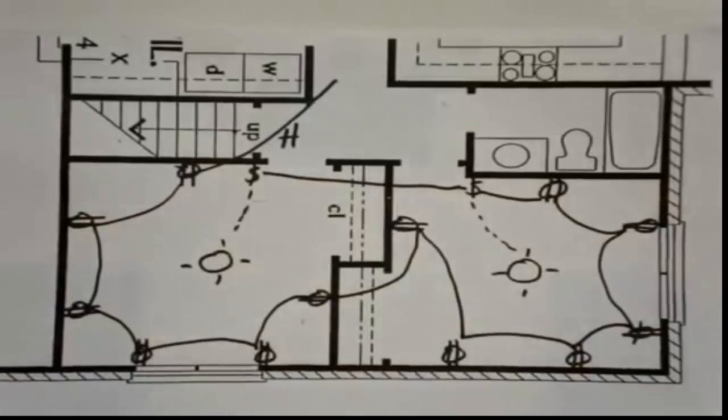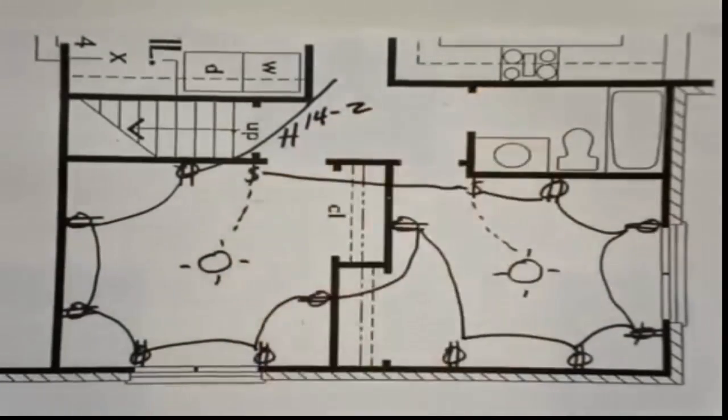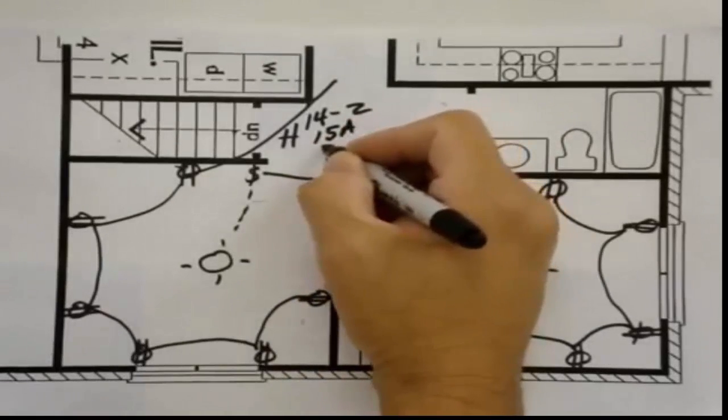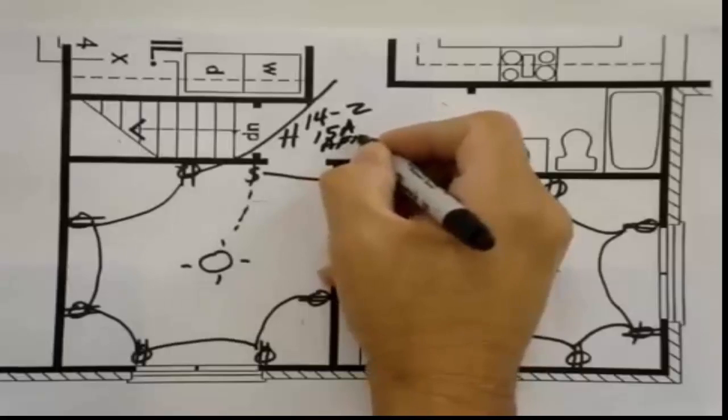All a continuous run. A home run is going to be with a 14-2 with a 15 amp breaker. An arc fault breaker. And we'll get into that in the wiring and the breakers for that in our other segment.